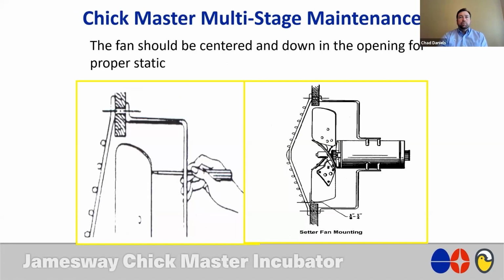So what we focus on with position is, when you look at these two illustrations, the one on the right, we really want this motor to be centered in the opening. So we have the same spacing from the fan board down to the edge of the blade on both sides. And then the goal is to get the bottom of that fan blade basically equal to or even with the bottom of the fan board. And that creates a spacing here that allows this blade, as it rotates, to build static and force the air down and not allow it to bleed out off of the tip of the blade.